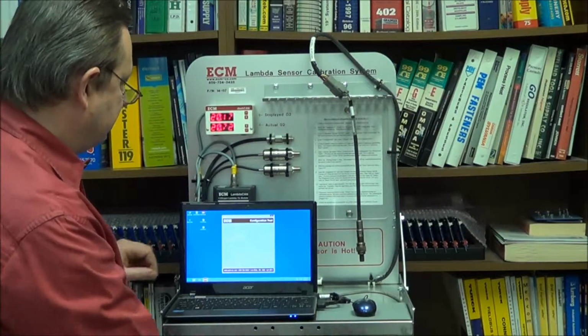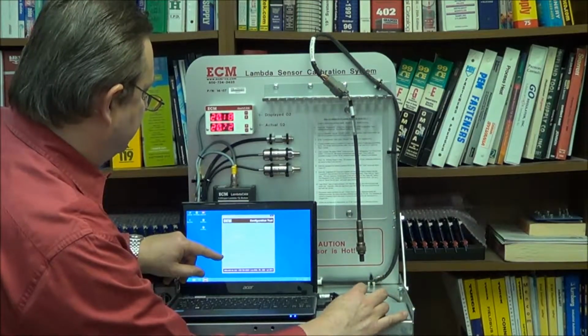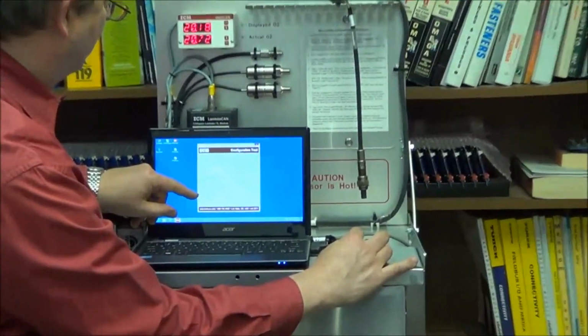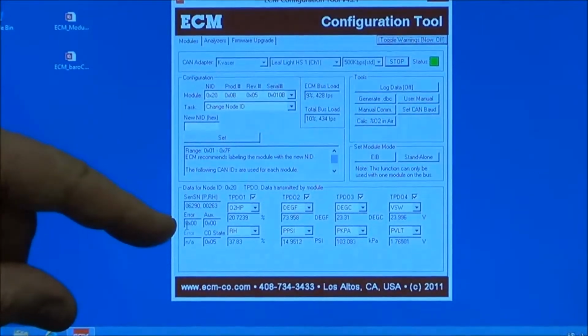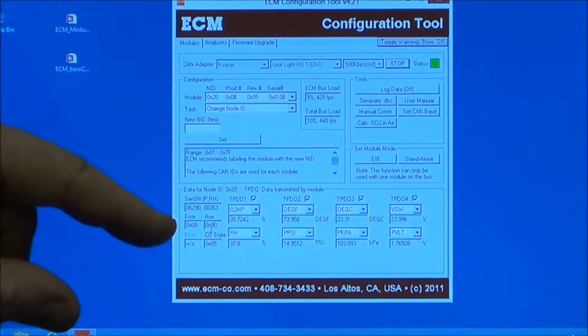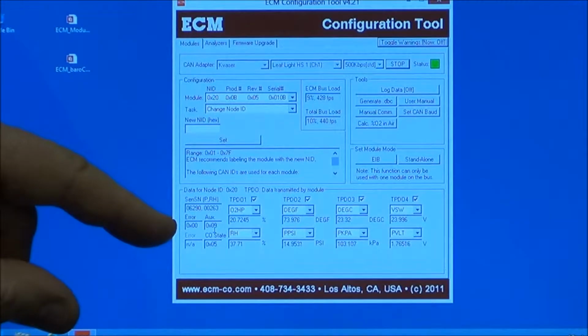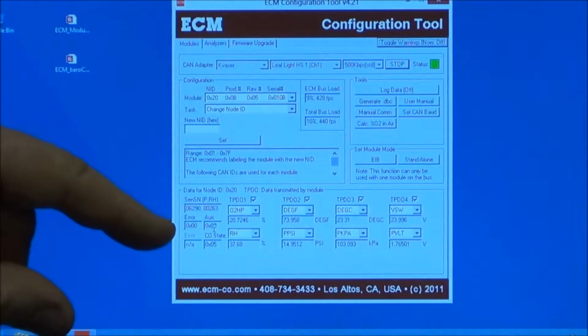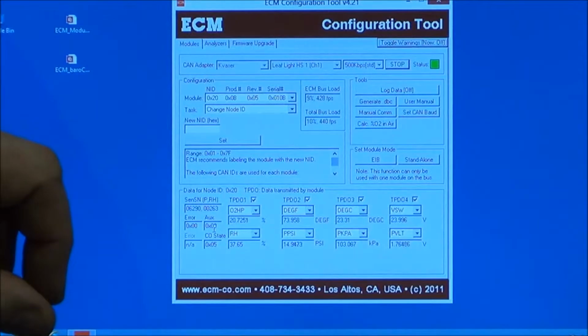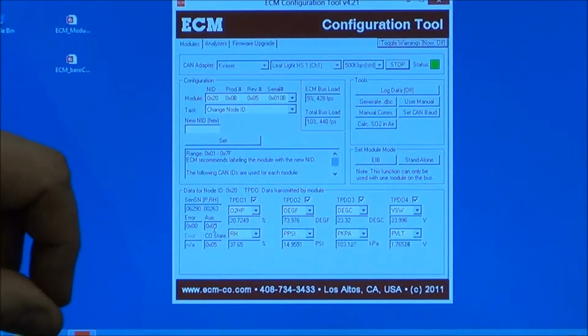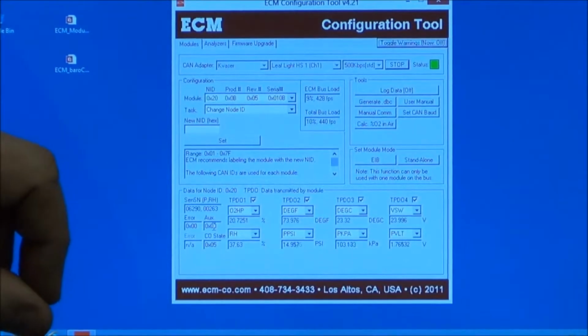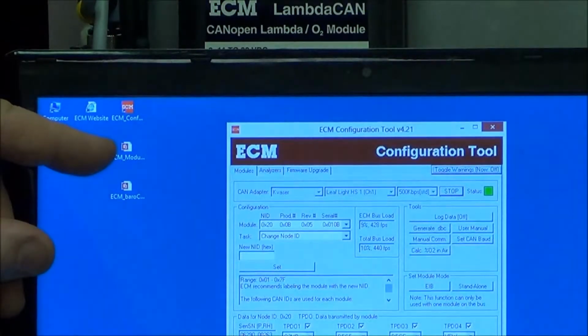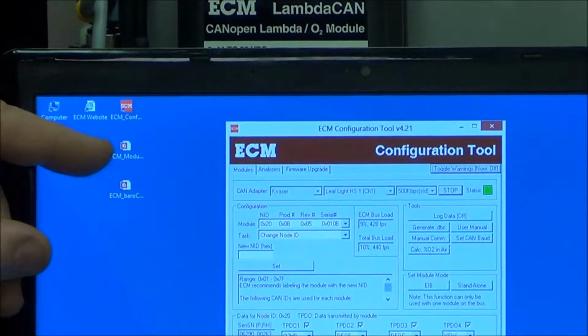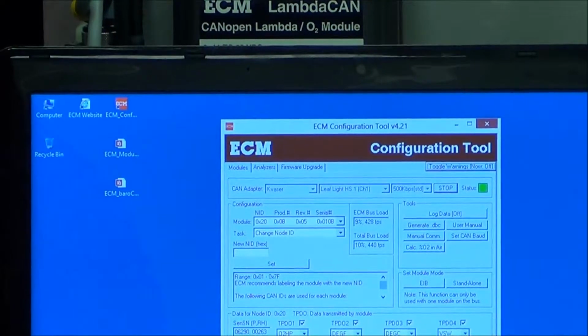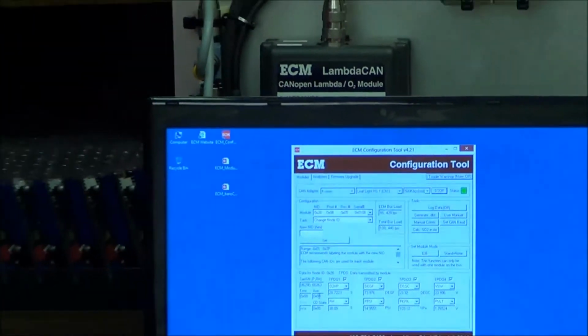After 1 minute, after the sensor's up to temp, read in the bottom corner the error code, which here is 0x00, which means the sensor is okay. If you don't get a 0x00, it means the sensor is broken and cannot be used. Error codes are described on page 14 of the ECM module configuration software manual, which is right here on the desktop. Now you have to wait for 1 hour until the number stabilizes.